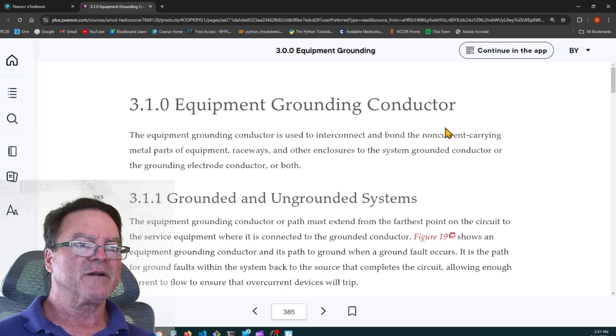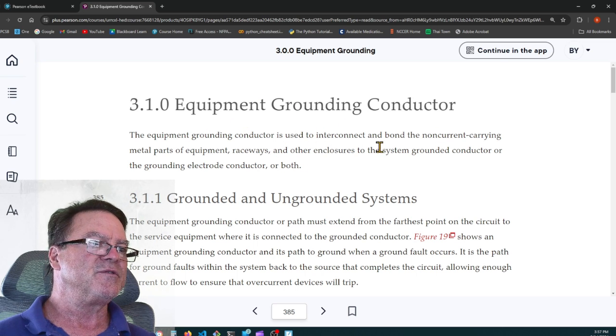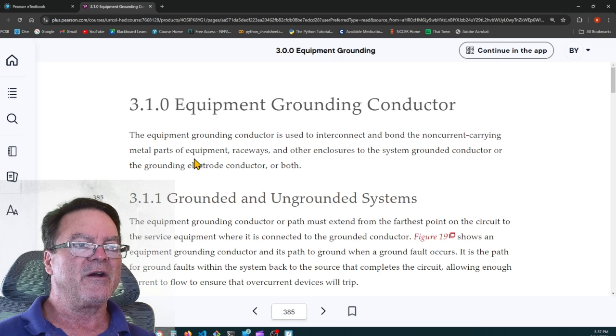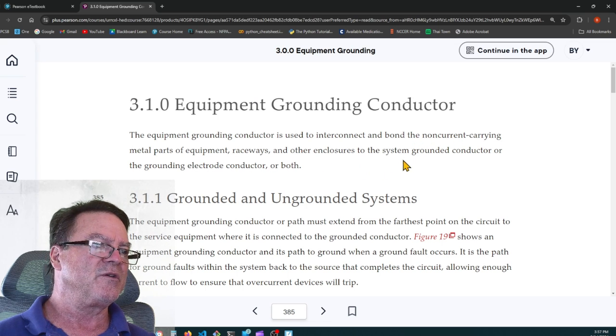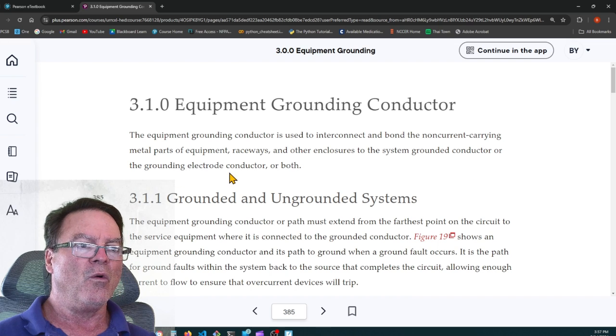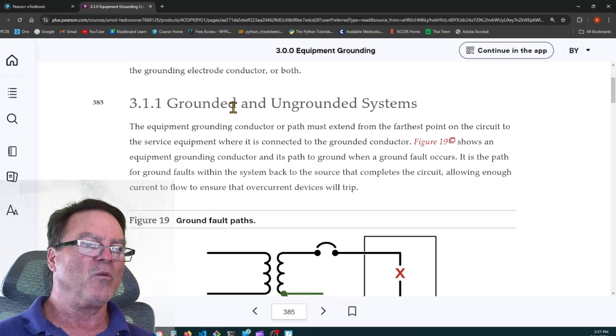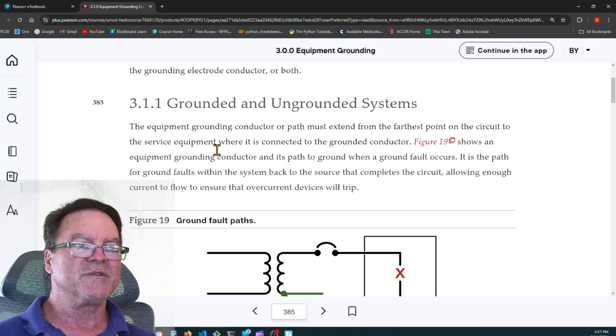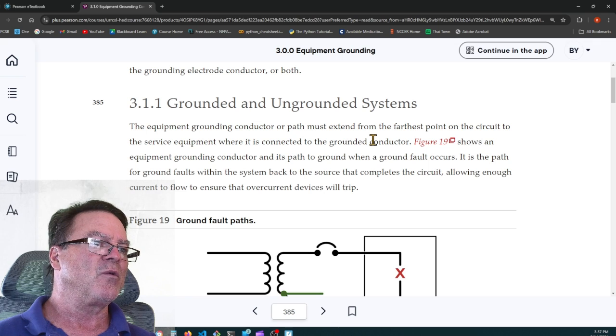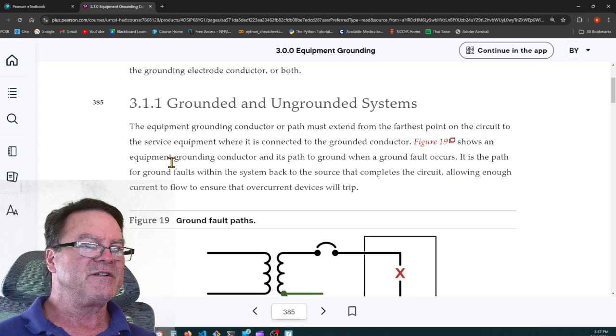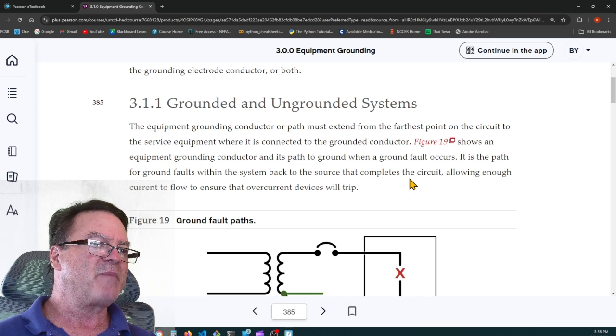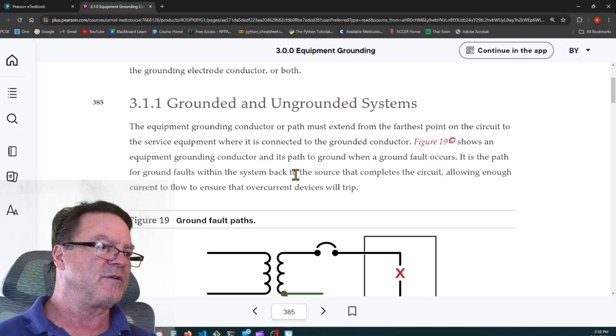3.1.0, the equipment grounding conductor. The equipment grounding conductor is used to interconnect and bond the non-current carrying metal parts of equipment, raceways, and other enclosures to the system grounded conductor or to the grounding electrode conductor, or both. 3.1.1, grounded and ungrounded systems. The equipment grounding conductor or path must extend from the farthest point of the circuit to the service equipment where it is connected to the grounded conductor. Figure 19 shows an equipment grounding conductor and its path to ground when a ground fault occurs.